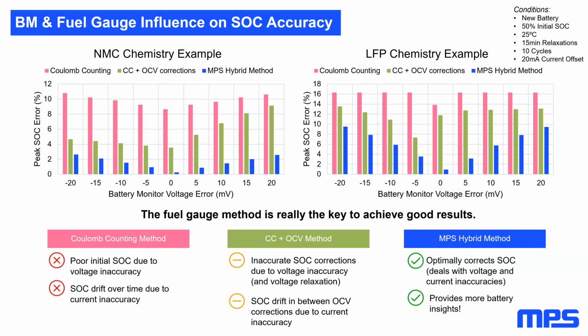On the other hand, the Coulomb counting plus open circuit voltage-based correction method, shown in green, relies on voltage measurements only during relaxation, where cell voltages converge to the open circuit voltage. Results of this method outperform Coulomb counting since it can correct the SOC drift over time. However, these corrections are affected by voltage measurement error, relaxation times, and the open circuit voltage characterization.